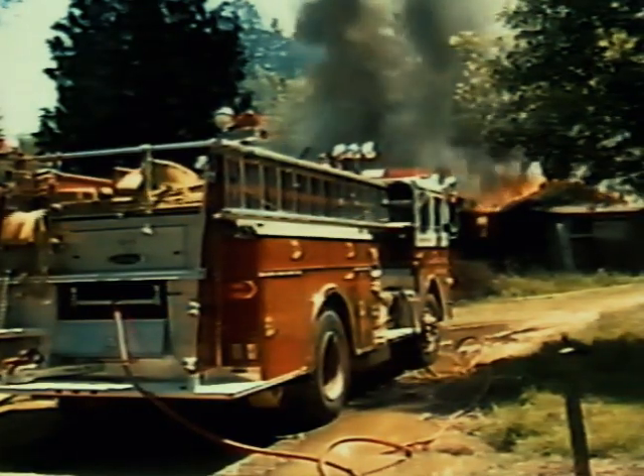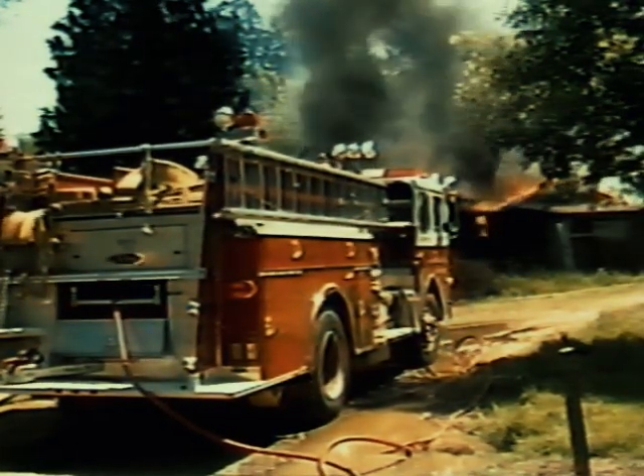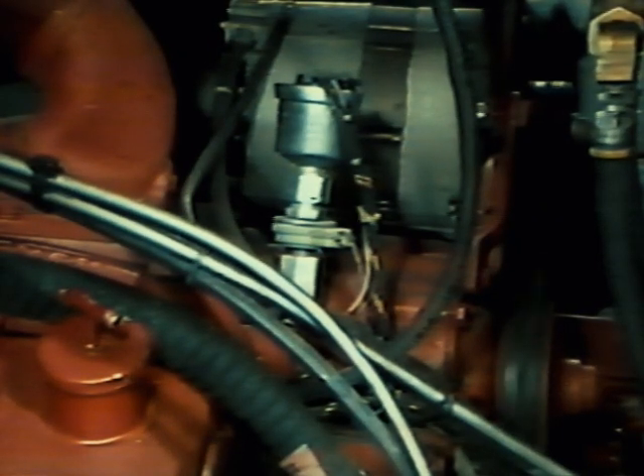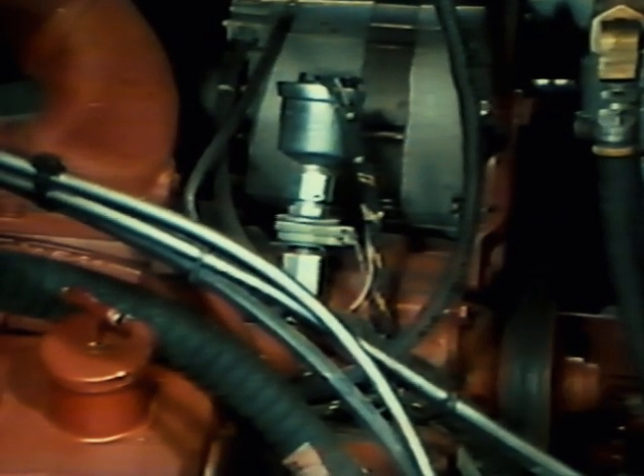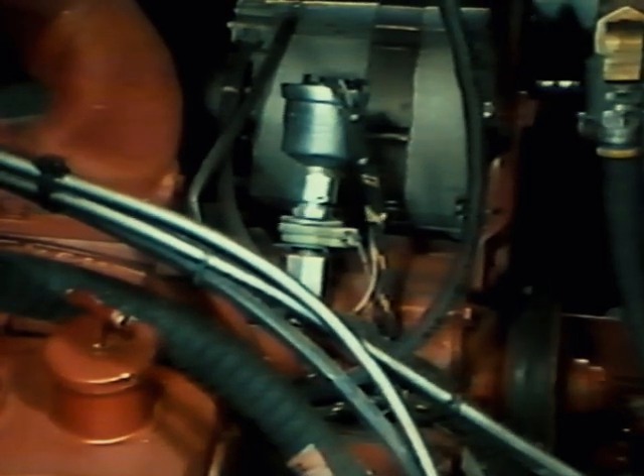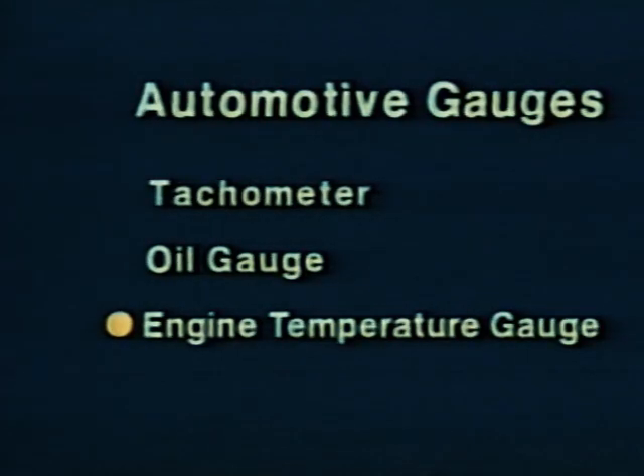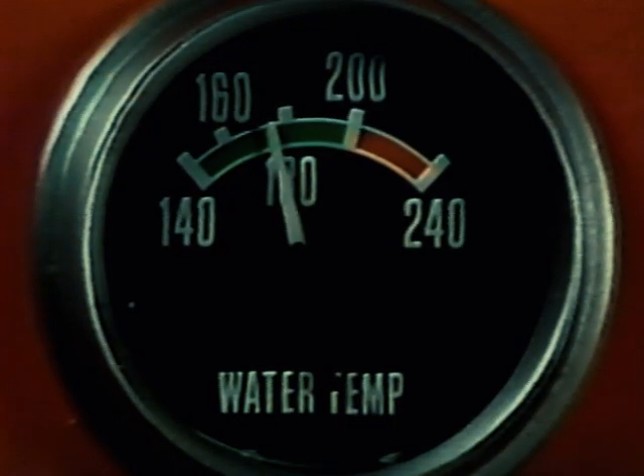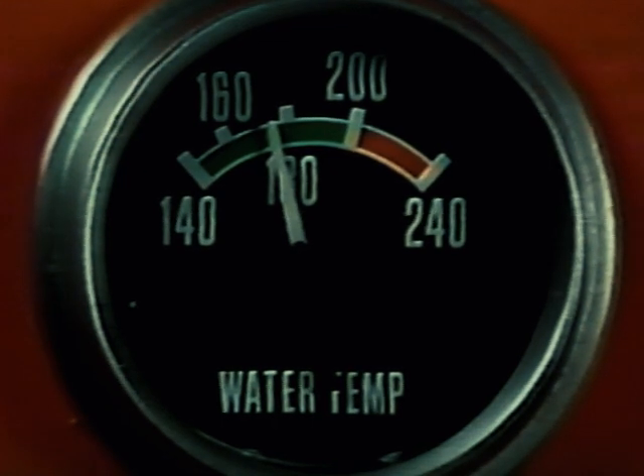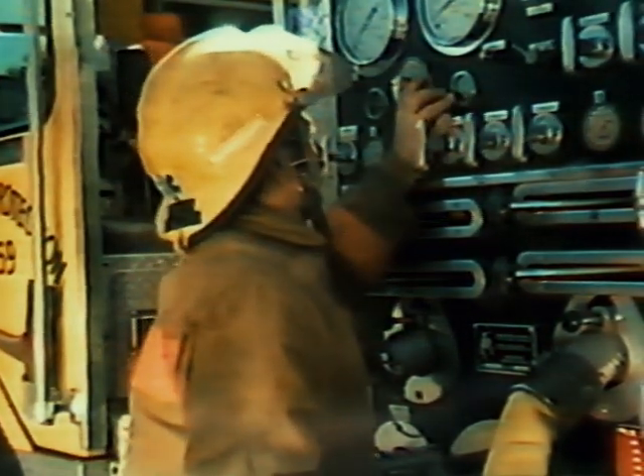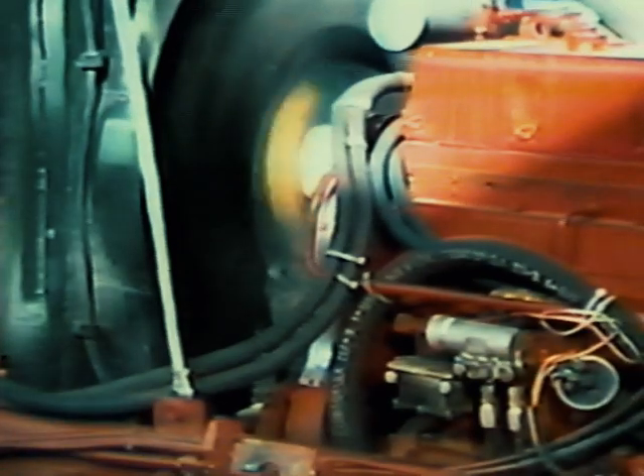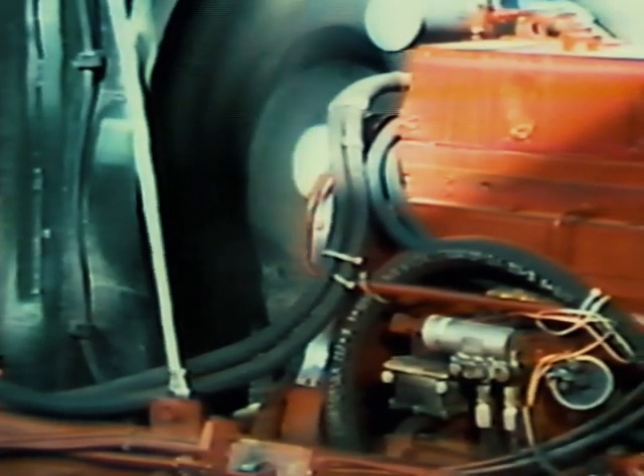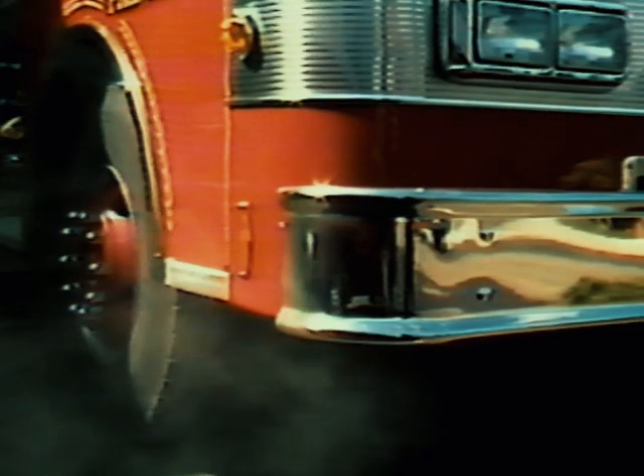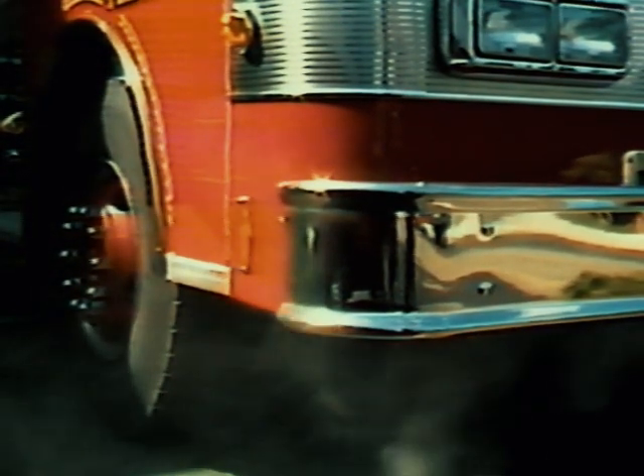Some pumpers may have a low oil pressure shutdown switch that shuts the engine down automatically if oil pressure falls below manufacturer's operating pressure. The engine temperature gauge is another automotive gauge found at the pumping station. The temperature gauge indicates the operating temperature of the engine in Fahrenheit or Celsius. This gauge should be monitored closely so that the engine operates at the proper operating temperature for maximum efficiency and to protect the engine from damage due to overheating.